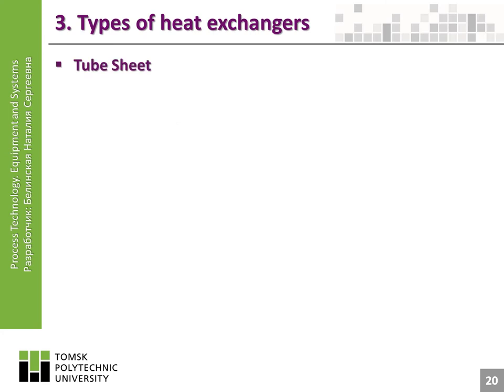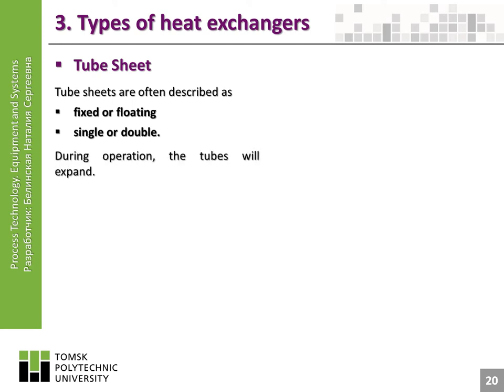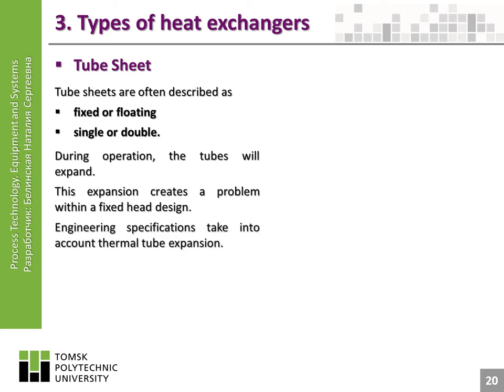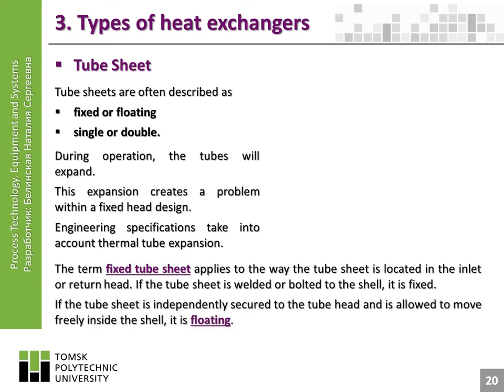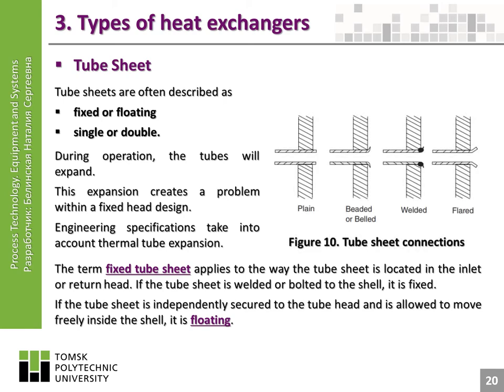Tube sheets are often described as fixed or floating, and single or double. During operation, the tubes will expand, creating a problem within a fixed head design. Engineering specifications take into account thermal tube expansion. The term fixed tube sheet applies to the way the tube sheet is located in the inlet or return head. If the tube sheet is welded or bolted to the shell, it is fixed. If the tube sheet is independently secured to the tube head and is allowed to move freely inside the shell, it is floating. Sheet connections include plain, beaded or belled, welded, and flared.